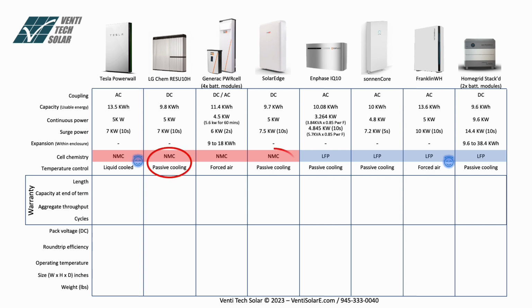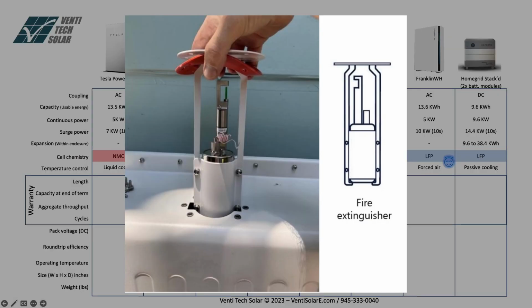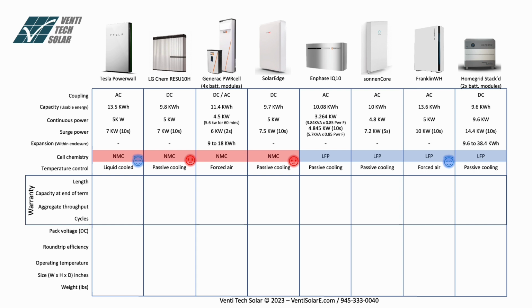Now LG Chem and SolarEdge will get a frowny face for their passive cooling NMC technology, although the SolarEdge comes with the fire extinguisher at the top of the unit. And it's mechanical or chemistry based. So when the cells get too hot, or when the system gets too hot, the fire extinguisher will kick in and will dissipate the fire inside the enclosure. I would say it's a good patch. I would not want my system to be dependent on that. It's a step above what LG is doing, that has no fire extinguisher, passive cooling on NMC cells, but I would not recommend it either.